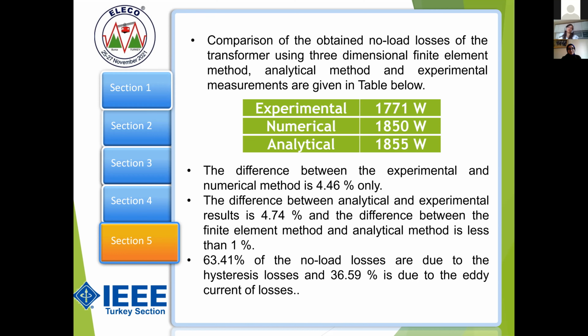We can see from the result that the difference between the analytical and experimental result was like 4.74%, and the difference between the finite element method and the analytical method was less than 1%. So we can continue with the other work as well. We can add the harmonics in the voltage to see how harmonics affect the overall core losses. As I told you, most of the no-load losses were from the hysteresis losses: it is 63.41%, and for the eddy current losses, it is 36.6%.